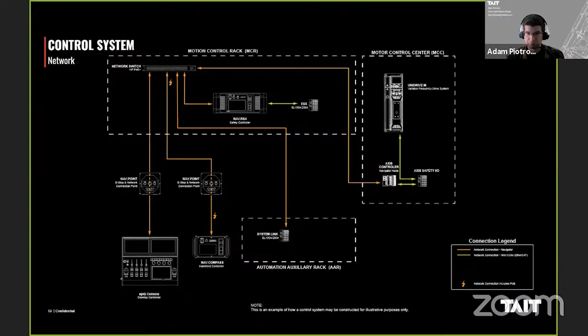I keep harping on safety, and I think it's important in any automation system to ensure things are safe and reliable, especially when it comes to the shutdown path or the e-stop system. This is done with a combination of networked IO, depicted by the yellow lines, and hard IO, because ultimately it comes down to a button or a limit switch that needs discrete wires run to it.